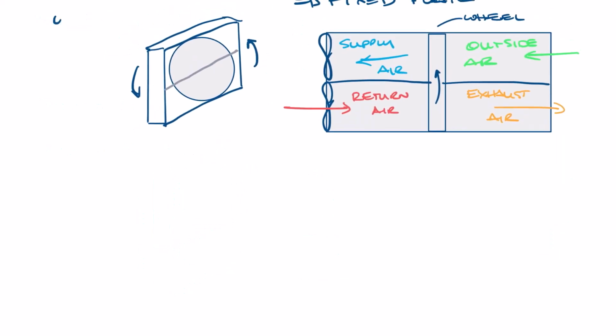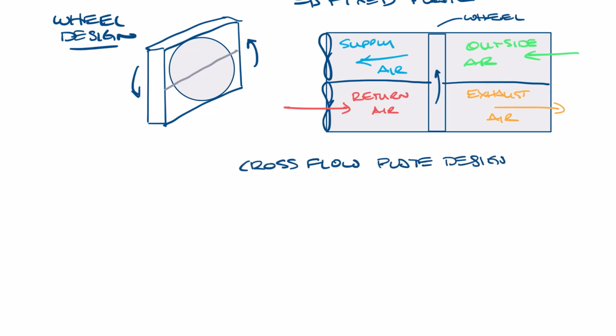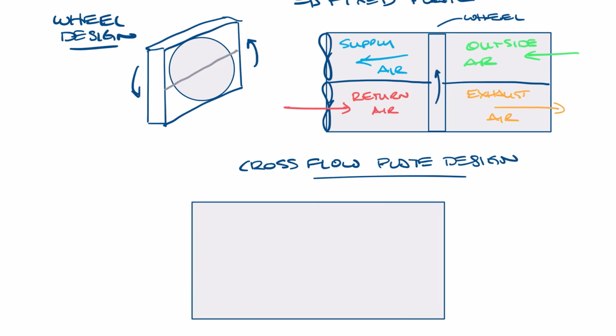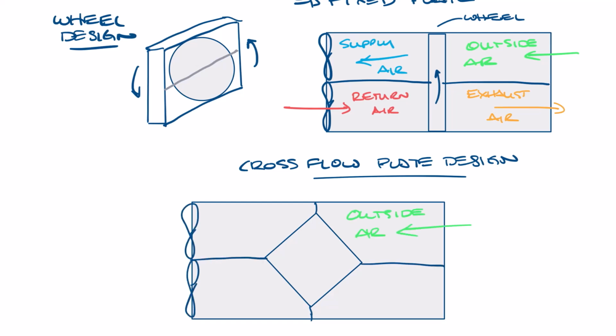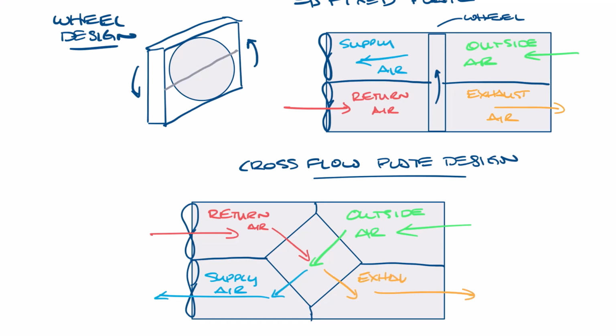So let me make room and look at the fixed plate design. There's two types of fixed plate designs, crossflow and counterflow. So the crossflow design looks like this. We'll draw the cabinet, and the plate section is here in the middle, and then all these quadrants are separated. We have fans over here, so the outside air enters here and passes through the plate in this direction. Then this fan blows the supply air out. The return air comes in here and passes through the plate in this direction, and it's exhausted out here.